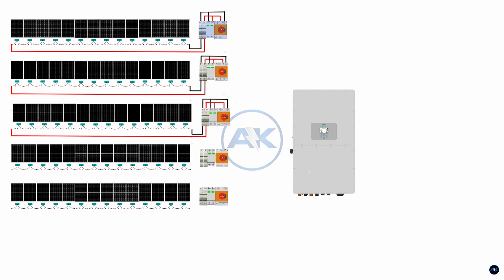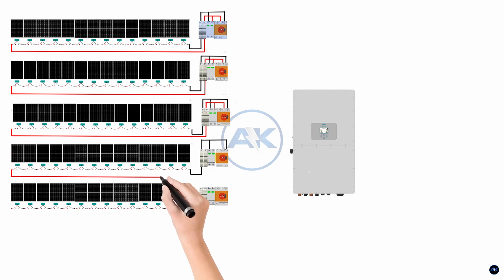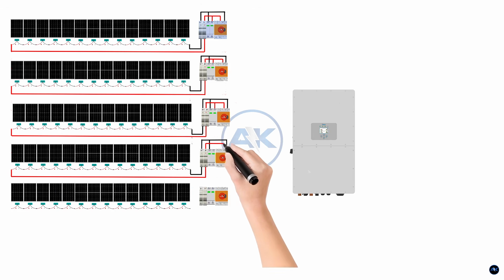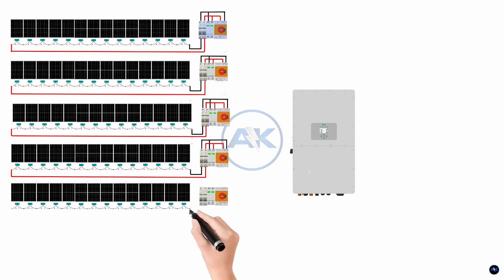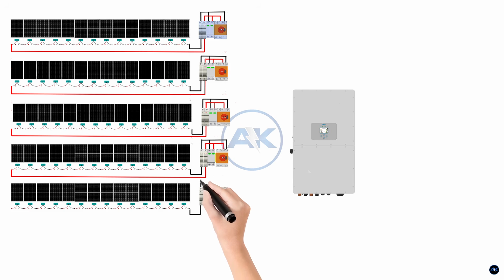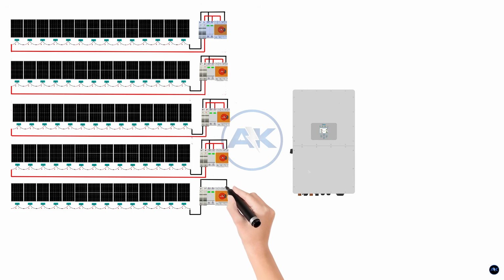This is one complete solar string. With 14 panels in series, the string voltage stays safely below the inverter's 1000-volt DC limit, even in cold weather, and the current remains the same as a single panel. Repeat this exact process to create all 5 identical strings. Each string must be wired the same way, with the same number of panels and the same orientation.